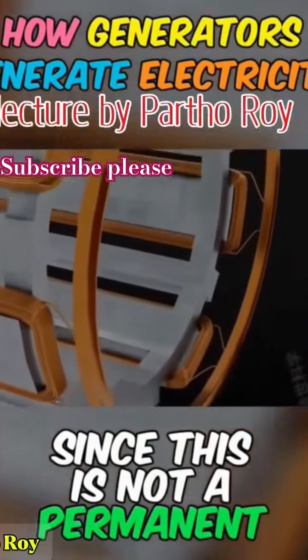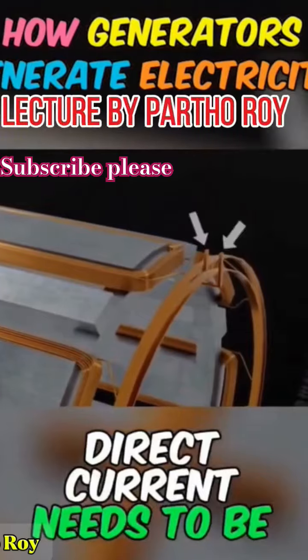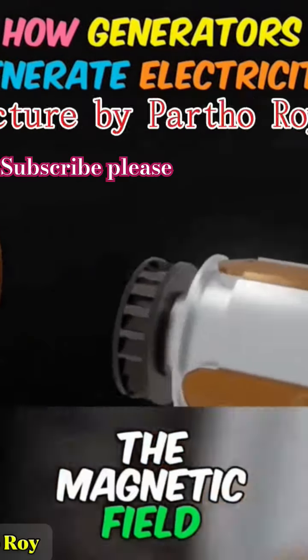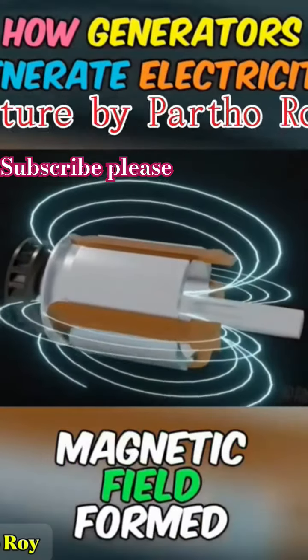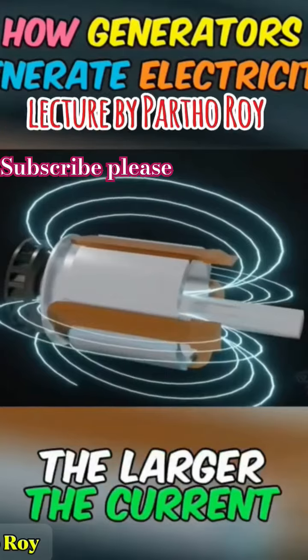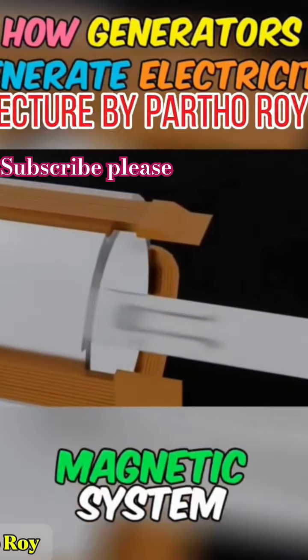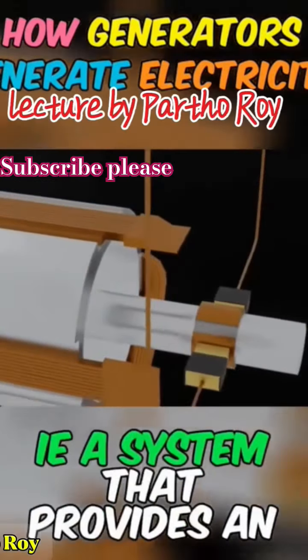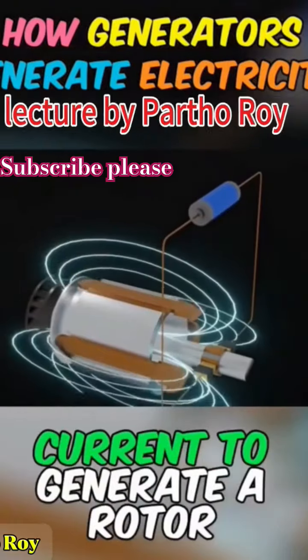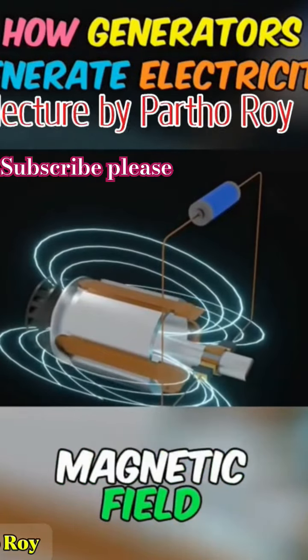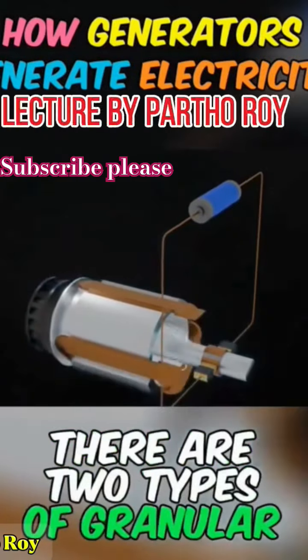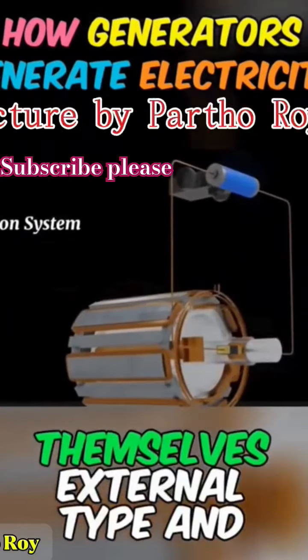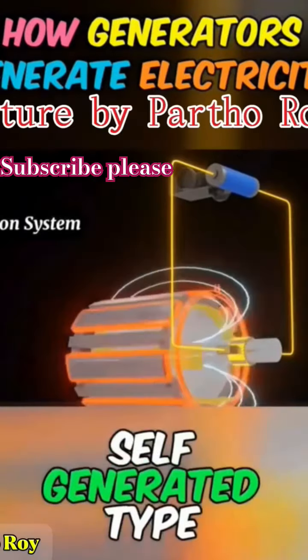Since this is not a permanent magnet, direct current needs to be passed to excite the magnetic field. The stronger the magnetic field formed, the larger the current. This is called an excitation system, i.e., a system that provides an initial current to generate a rotor magnetic field. There are two types of excitation systems themselves: external type and self-generated type.